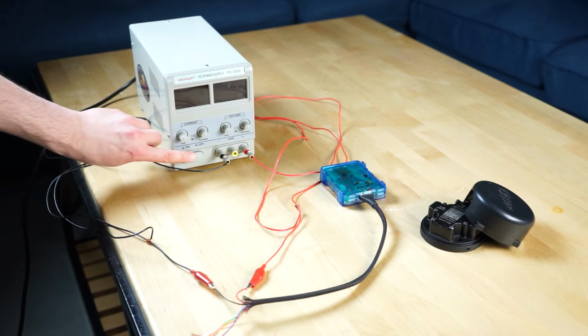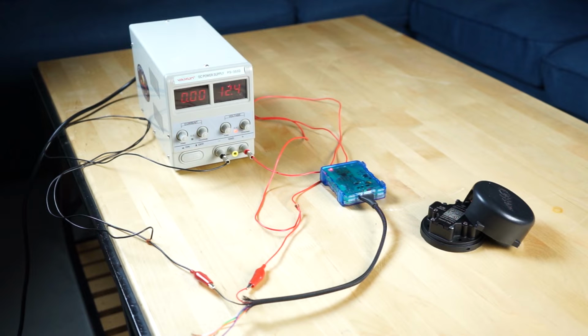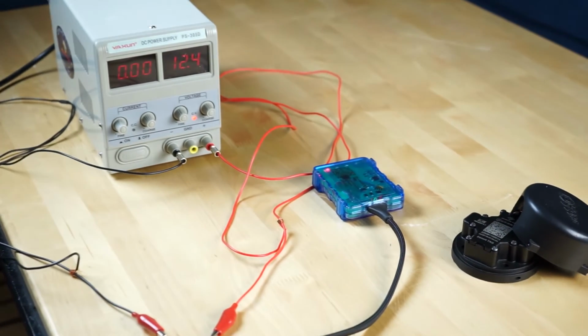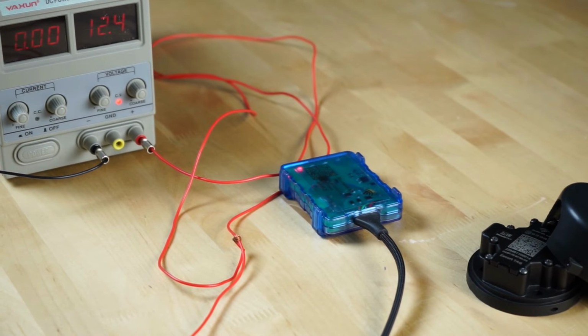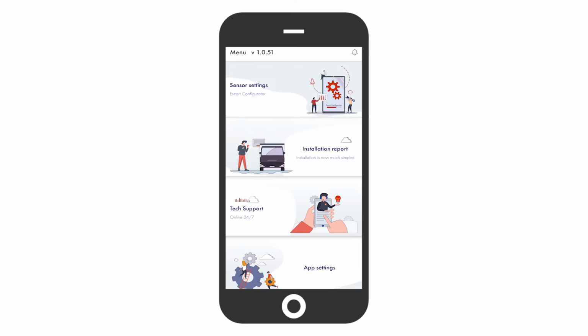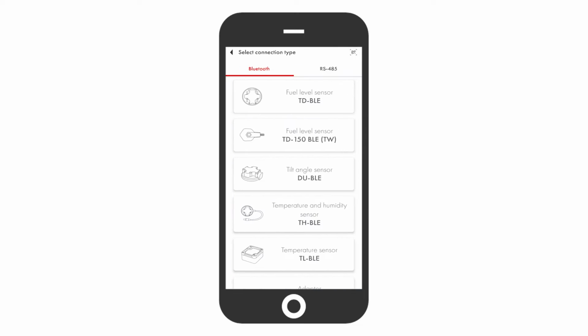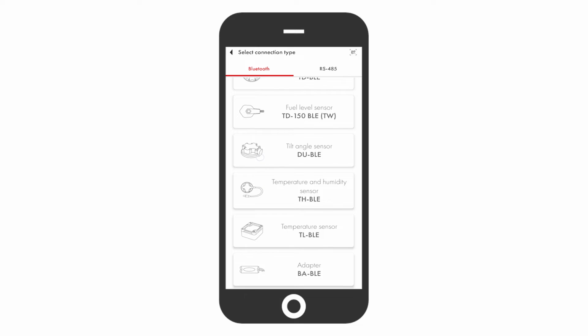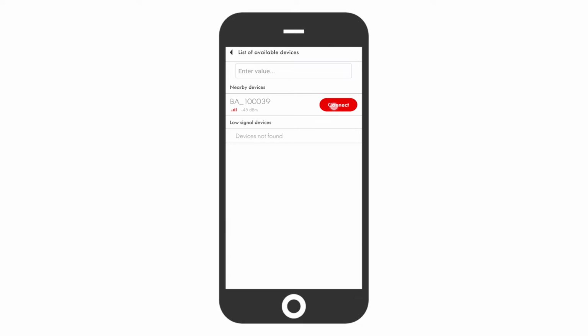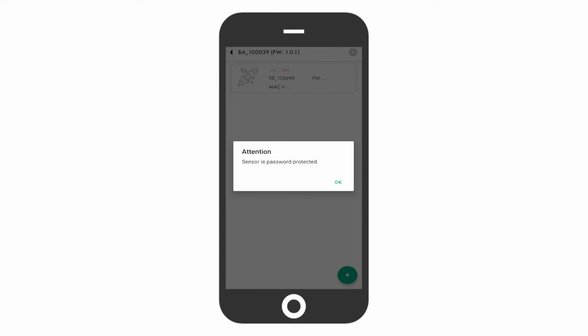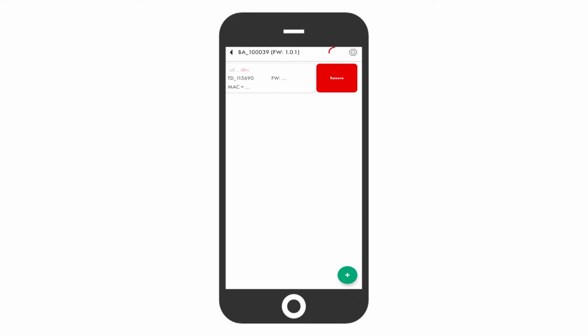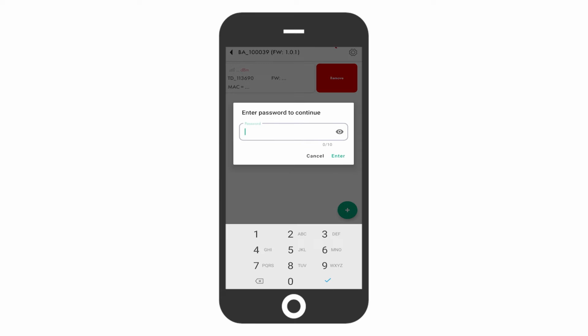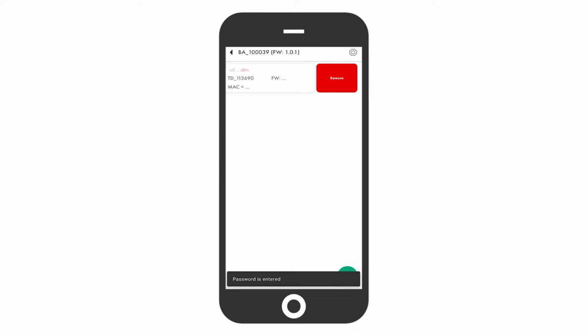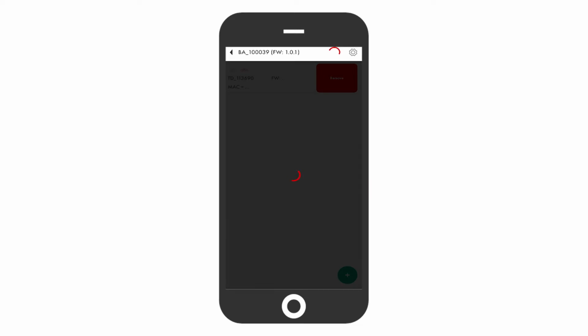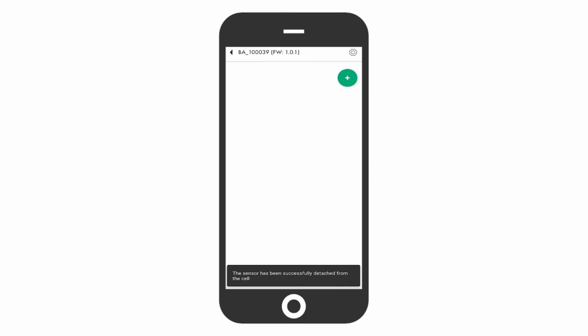To configure the adapter, you just need to connect its black and red wires to a power supply of 12 to 36 volts and run our app. In the app, go to the sensor settings and select BA BLE device type. Then press connect. The app will require you to set up or enter a previously set password. The password protects the base from any attempts to tamper with its settings by any unauthorized third party.